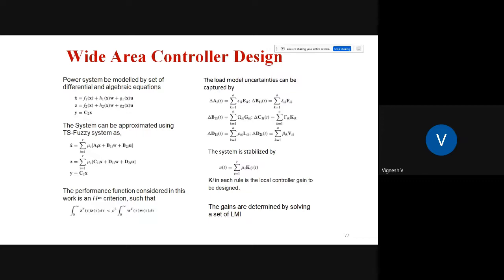So we model the controller using a fuzzy logic based controller. Why should we go for a fuzzy logic controller? The answer is because the load model parameters could change. So in order to capture the variation of the load model parameters, we use a TS fuzzy system, and the system is stabilized by an output feedback controller, which is shown in this equation: U of t equals the sum over i equal to 1 to R of mu i Ki y of t, where y of t is the measured output signal. And we are going to compute the Ki's as the controller gains for this particular type of controller.